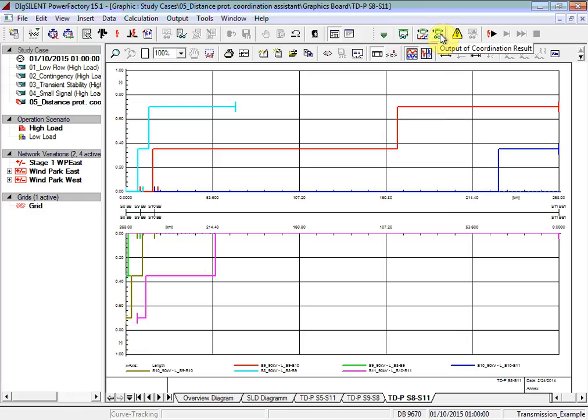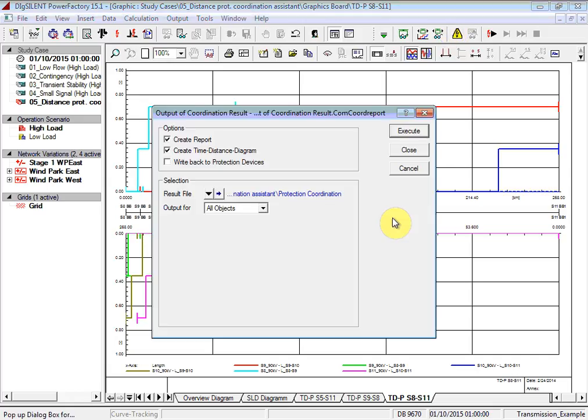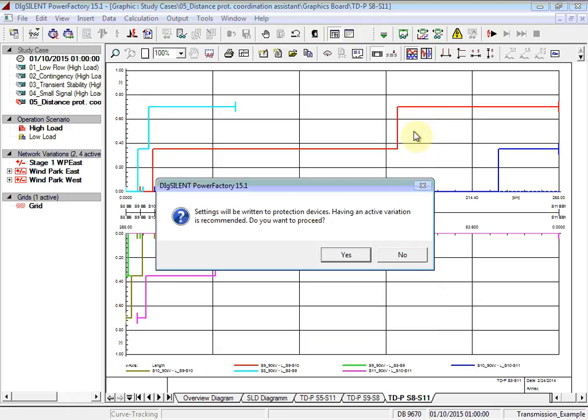Press the Output of Coordination Result button again. And now choose the option Write Back to Protection Devices. Deselect the other options if you don't want them to appear. Select Execute. Here it is saying that settings will be written to protection devices and it is recommended to activate a variation. We will take this advice on board and create a variation.